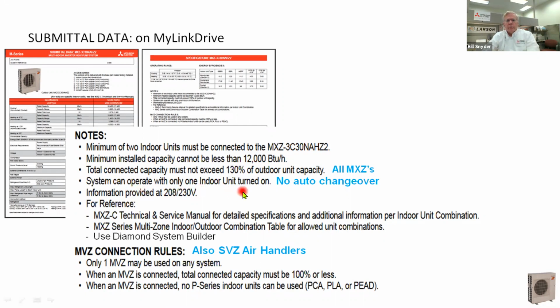Also on MXZ units, you should not do auto changeover. Auto changeover is where it switches from heating to cooling. All zones should be in heat or all zones should be in cooling. Auto changeover does not work. If you're going to put this in a small commercial building and you've got a server room that's going to constantly call for cooling and everybody else is going to call for heat, this will not work. It will not switch over and you're going to have an unsatisfied person. You'd be better off putting a separate unit in that server room.